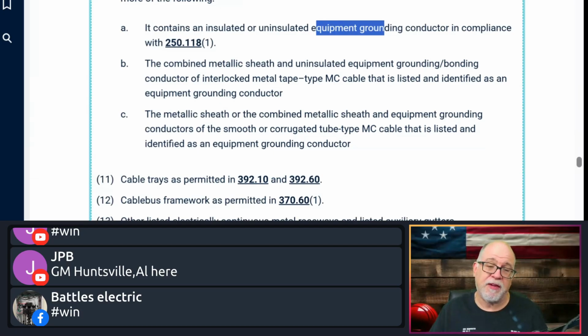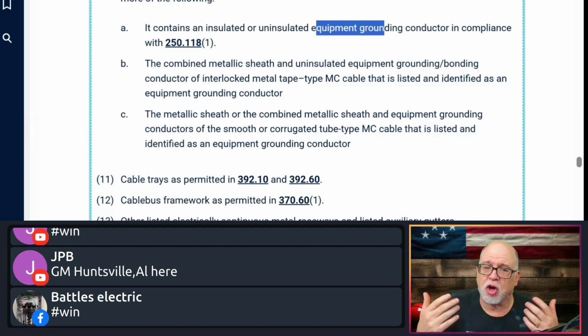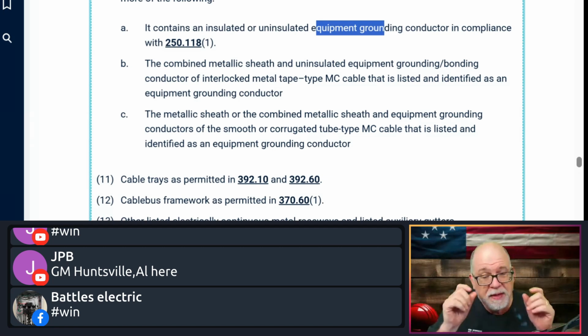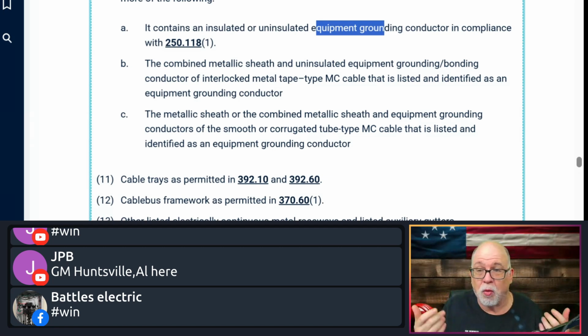Now, most manufacturers will insulate their equipment ground in smaller MC products, but when you start getting to the bigger MC, like the feeder type MC, then we don't insulate it because it's extra cost that is unnecessary. PVC costs money. And so why is a manufacturer just going to give that away when it doesn't matter as far as the minimum safety standard? It can be bare or insulated. Okay, that type of thing.